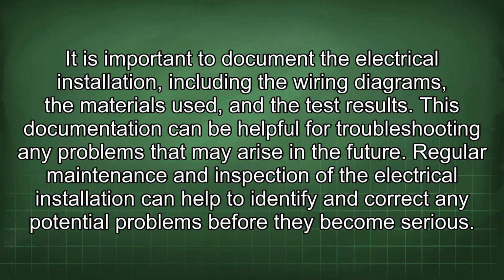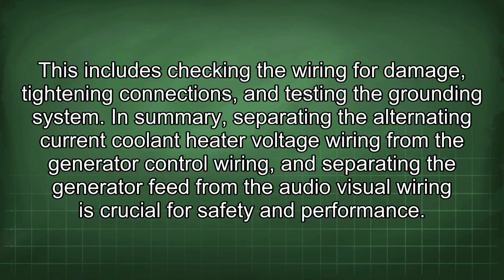It is important to document the electrical installation, including the wiring diagrams, the materials used, and the test results. This documentation can be helpful for troubleshooting any problems that may arise in the future. Regular maintenance and inspection of the electrical installation can help to identify and correct any potential problems before they become serious. This includes checking the wiring for damage, tightening connections, and testing the grounding system.